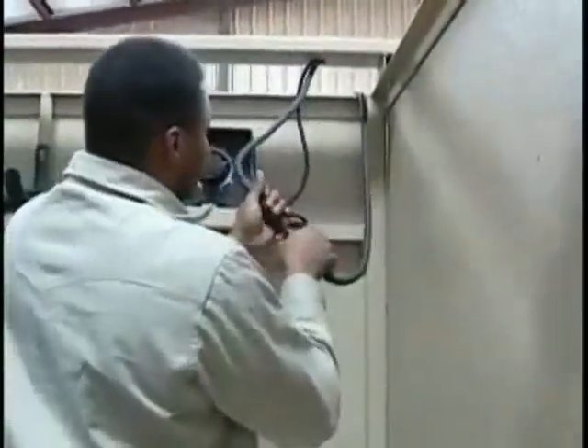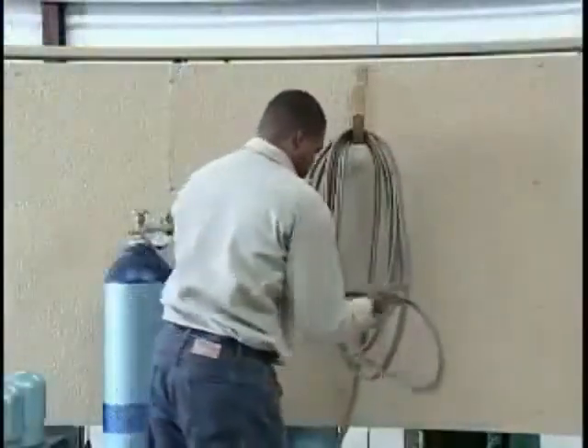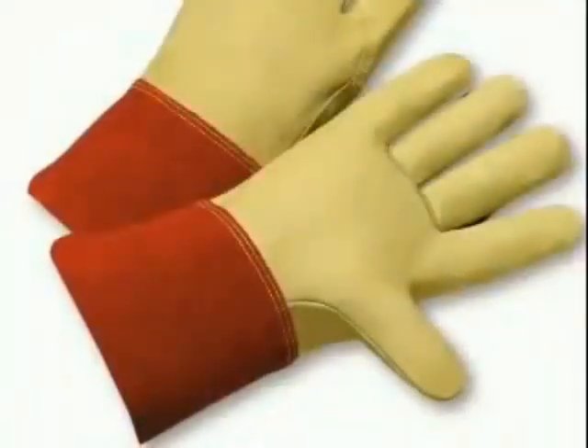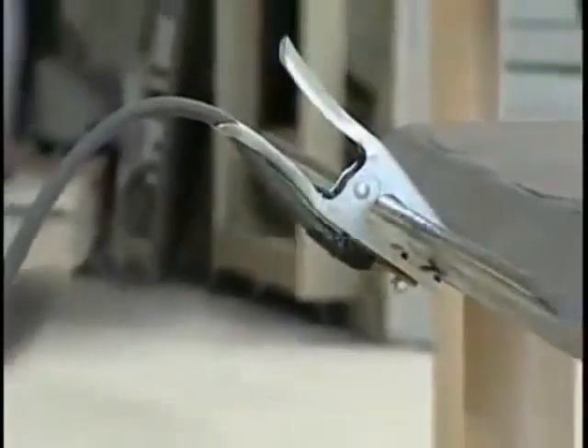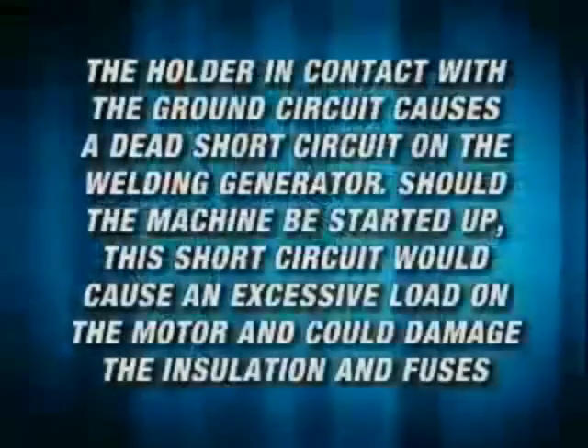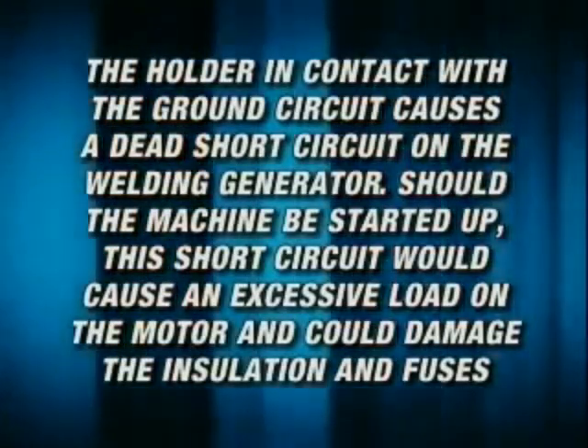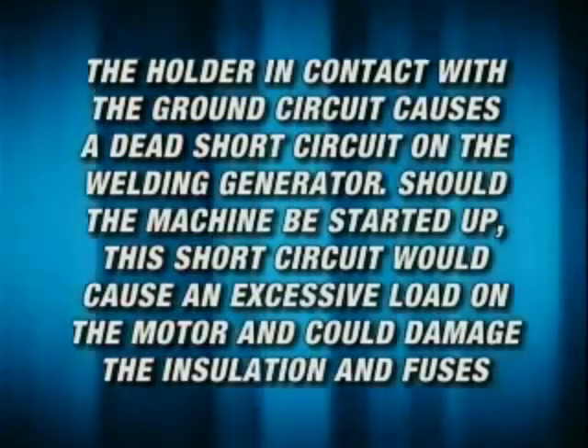When welding is to be interrupted for any substantial period of time, such as during lunch or overnight, OSHA requires that the machine be disconnected from the power source, all electrodes be removed from the holders, and the holders be carefully placed so that accidental contact cannot occur. When changing electrodes, the worker must be on a dry surface and wear gloves. The electrode holder must never be left in contact with the tabletop or other metallic surfaces in direct contact with the welding ground; an insulated hook or holder should be provided. A holder in contact with the ground circuit causes a dead short circuit on the welding generator.